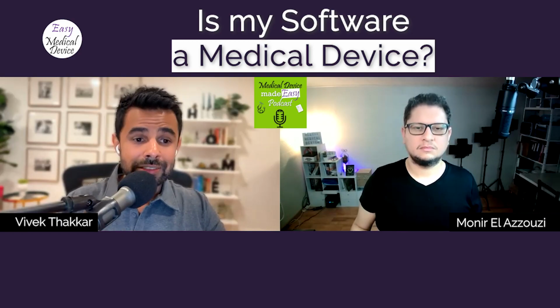When we say SaMD, that means it is a standalone software that has a medical purpose. It's not within a hardware, or it is not helping a hardware to achieve its purpose. It is achieving that purpose by itself. So that is the difference. And this is, by definition, called software as a medical device. However, once you have the software inside a medical device, you call it software in a medical device, which is SiMD.